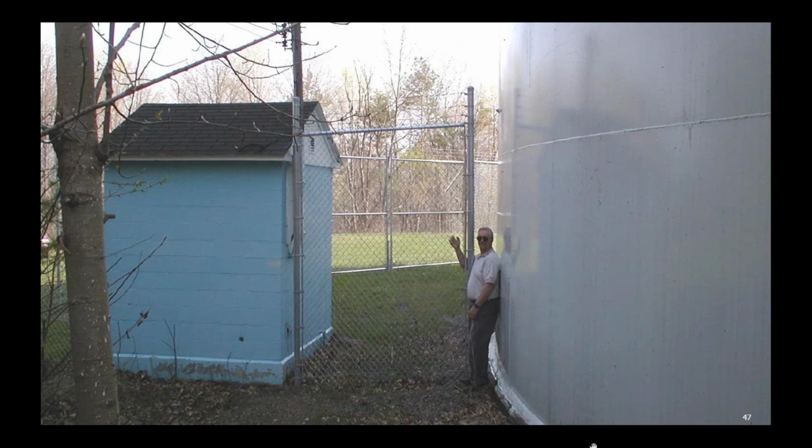Next. The next one was one that our state director and I had gone to. It was a brand new water plant at the time. Once again, that's kind of a wide space at the bottom of that fence. This is brand new equipment, brand new fencing, and they could have taken it down just a bit farther. It might be a little nitpicky, but don't have razor wire at the top of your fence so somebody can get in underneath your fence. Next.